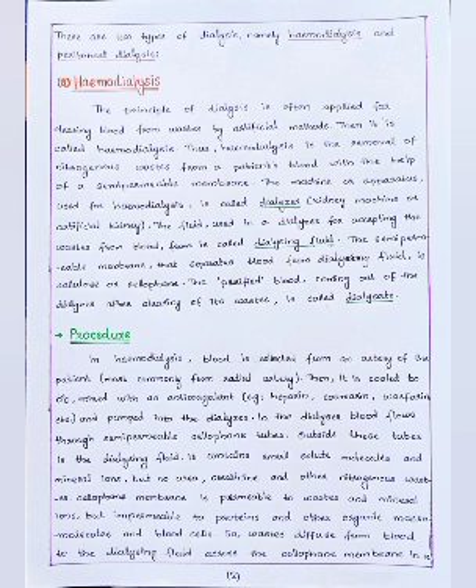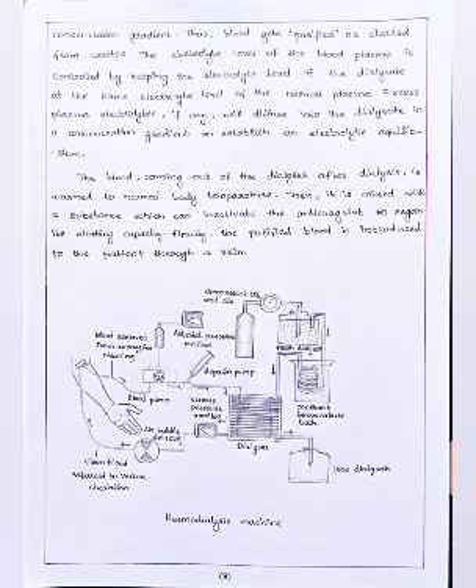Thus, blood gets purified or cleared from wastes. The electrolyte level of the blood plasma is controlled by keeping the electrolyte level of the dialysate at the same electrolyte level of the normal plasma. Excess plasma electrolytes, if any, will diffuse into the dialysate in a concentration gradient to establish an electrolyte equilibrium. The blood coming out of the dialyzer after dialysis is warmed to normal body temperature. Then it is mixed with a substance which can inactivate the anticoagulant to regain its clotting capacity. Finally, the purified blood is introduced to the patient through a vein. The diagrammatic representation of the processes is given on the screen.